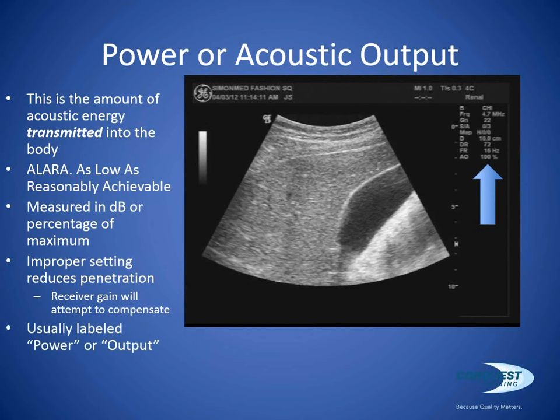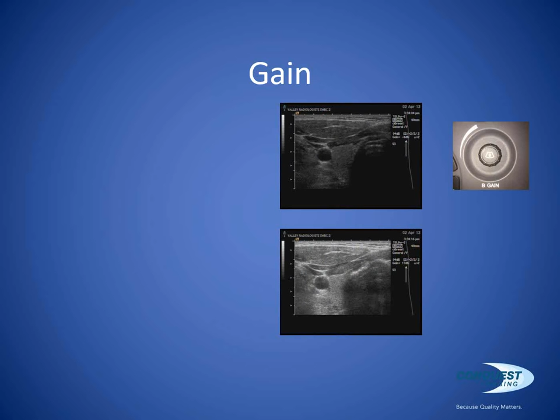It's usually labeled, the button is usually labeled power or output on systems. Gain. This is the other half of acoustical output. This is the amount of amplification of the received echo. So the transmitter pushes the energy into the body, the acoustic energy into the body. The energy bounces off structures within the body and then is reflected back to the transducer. The transducer, the elements on the transducer will vibrate, create an electrical pulse, and that pulse is amplified.